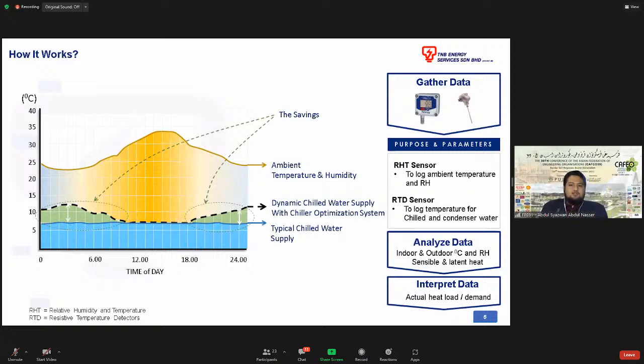How it works: if we look at the left side of the screen, there's a graph showing the typical chilled water supply temperature in Malaysia, normally between 6 to 7 degrees Celsius. Normally this is left fixed and untouched since the day they commissioned the chiller.